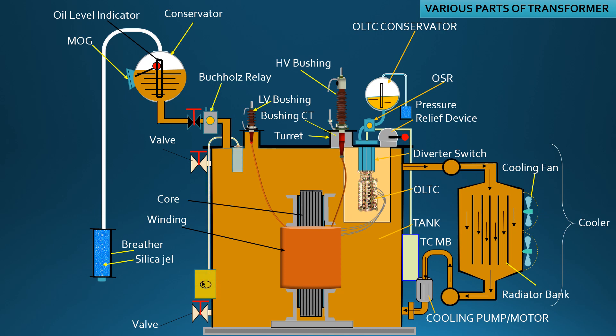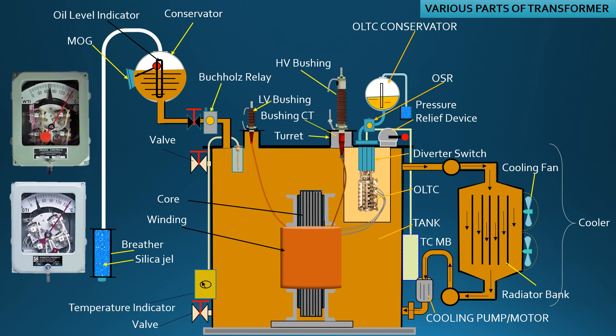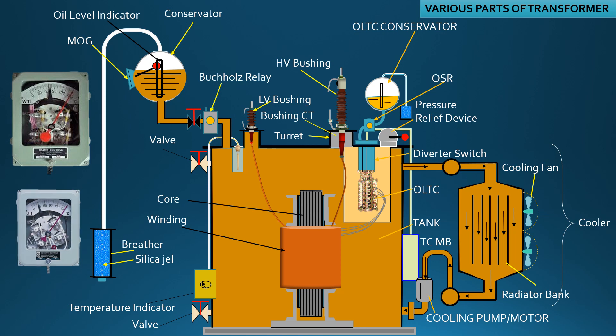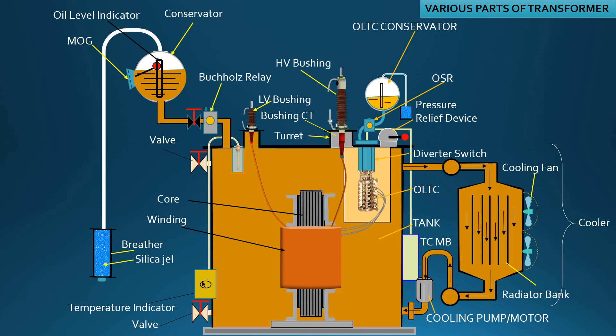Every power transformer is incorporated with winding temperature indicator and oil temperature indicator, WTI and OTI. The sensor bulb of the indicator is kept at the pocket where hot oil circulation is going on and near the winding.